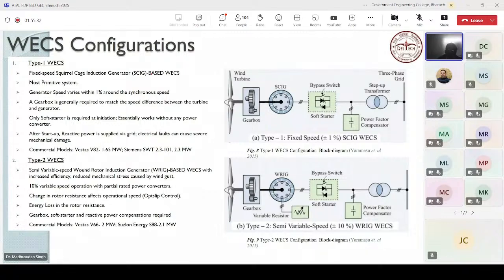I hope you all know that in 3-phase slip ring induction motors, if you want to vary the speed and torque, the rotor resistance control is effective, but it is not an efficient arrangement because you have to waste power in the rotor through resistance. But yes, through this you can have a control on the speed. So even 10% variation in speed you can adjust, and you can generate power, you can feed to the grid. So this is called type 2 arrangement.